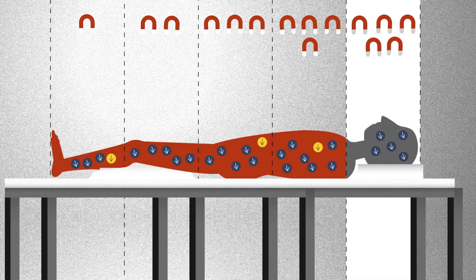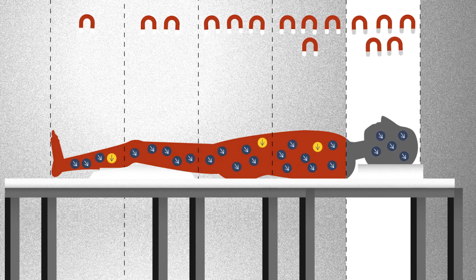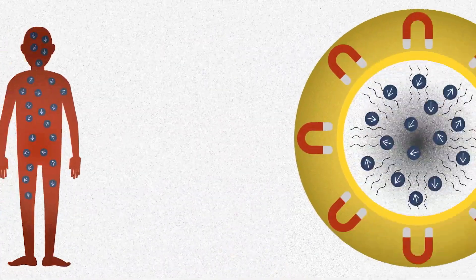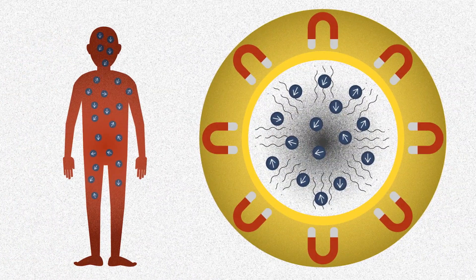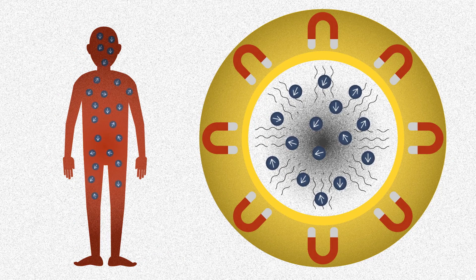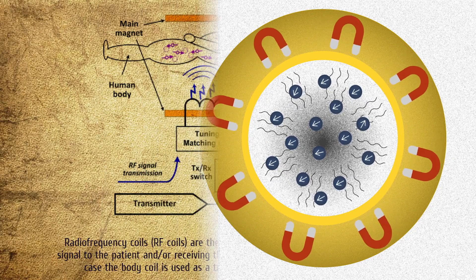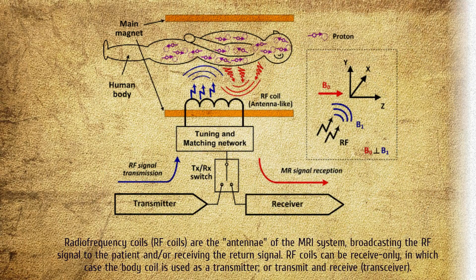The coil is usually built into the body of the scanner. The power of the transmitter is variable, but high-end whole body scanners may have a peak output power of up to 35 kilowatts and be capable of sustaining average power of 1 kilowatt.